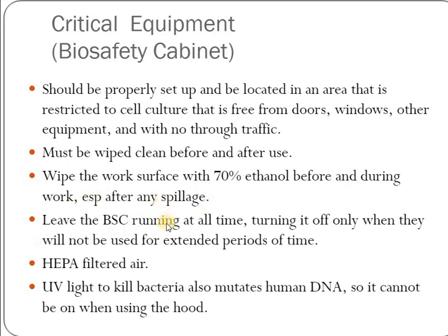The biosafety cabinet should always be kept running, and it has to be turned off only when it is not going to be used for extended periods of time. HEPA, high efficiency particulate air filtered air, should always be provided. UV light has to be supplemented to kill bacteria, but it also mutates human DNA, so it cannot be on when using the hood.